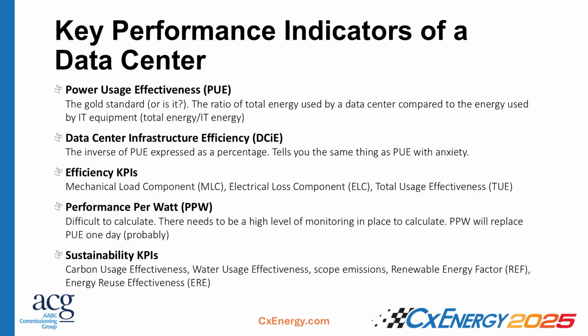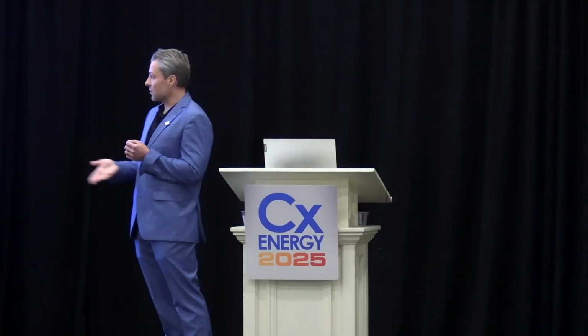Efficiency KPIs like MLC, ELC, and total usage effectiveness are coming into play too. The nice thing is they all use the same denominator—IT energy. So mechanical load component is all of your energy consumed in the mechanical systems in the building: pumps, CRAHs, chillers, whatever's used for HVAC and mechanical, divided by IT energy.